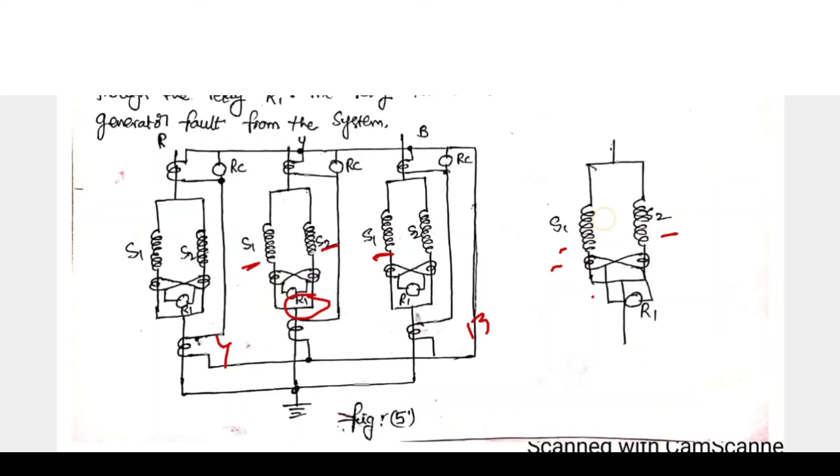If a short circuit develops between adjacent turns, say S1, if a short circuit appears in adjacent turns in between S1, the currents in the stator winding S1 and S2 are not equal. Because due to this short, this fault, what will happen, high current will flow.